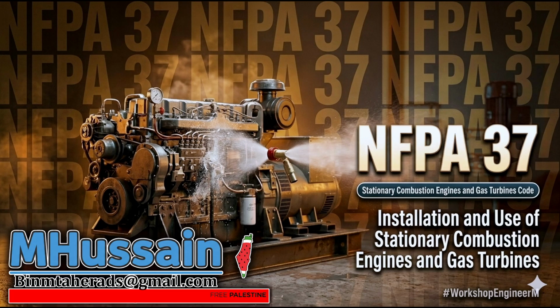So, for the firefighting engineers and facility owners listening, the big takeaway is that NFPA 37 is a system of redundant safeguards. Distance, ventilation, metallurgy, suppression, all working together to isolate inevitable mechanical failures. It's truly fascinating. Before we wrap up, I want to leave you, the listener, with a final provocative thought. The future of emergency power. Everything we've discussed today, NFPA 37, the iron pipes, the ventilation, is built around the physics of internal combustion. Liquid diesel, pressurized gas, 900-degree exhaust.